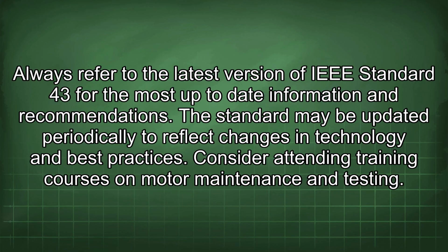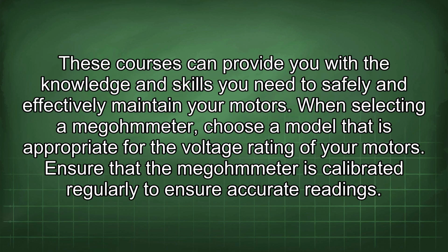Always refer to the latest version of IEEE Standard 43 for the most up-to-date information and recommendations. The standard may be updated periodically to reflect changes in technology and best practices. Consider attending training courses on motor maintenance and testing. These courses can provide you with the knowledge and skills you need to safely and effectively maintain your motors. When selecting a megohmmeter, choose a model that is appropriate for the voltage rating of your motors. Ensure that the megohmmeter is calibrated regularly to ensure accurate readings.